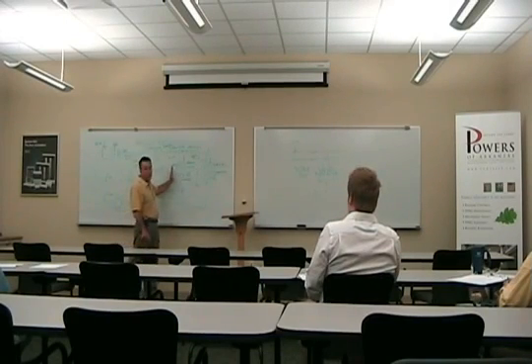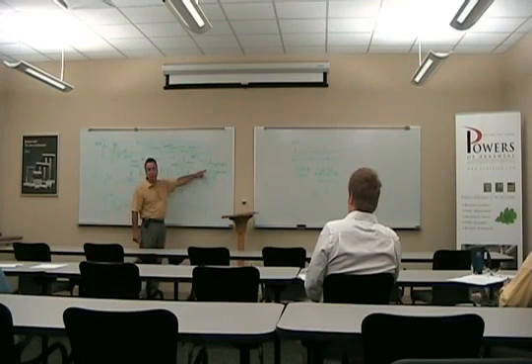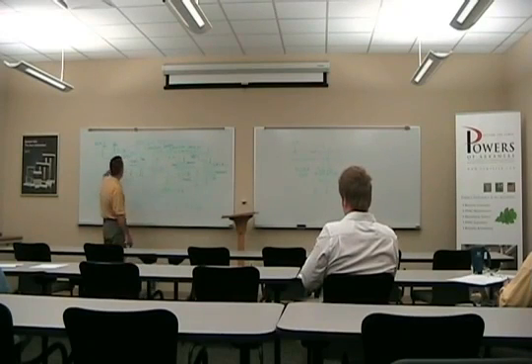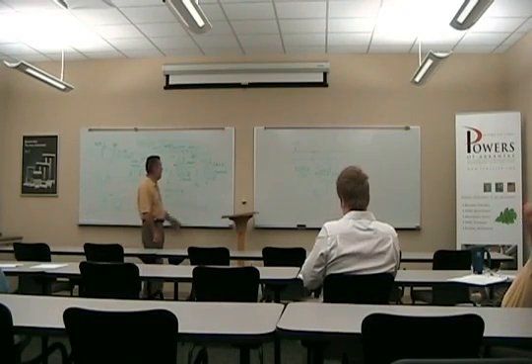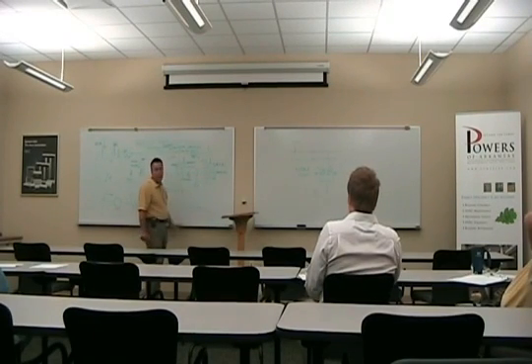So that's why you see mostly parallel operation. Because why run that fan in the summertime? Because that motor is generally a part winding motor operating at 50 or 60% efficiency. This is a larger motor operating probably 75, 80% efficiency, maybe even more. So that's one reason in the series. That's always running. This is only running in the wintertime.